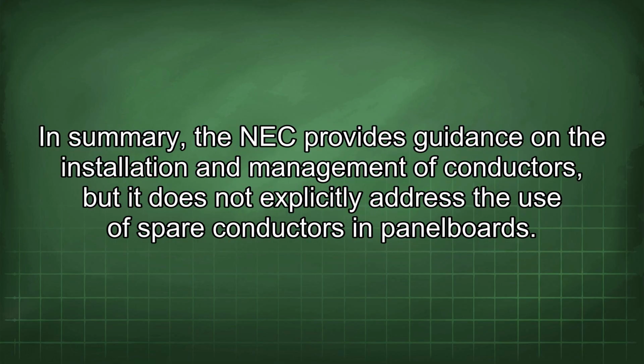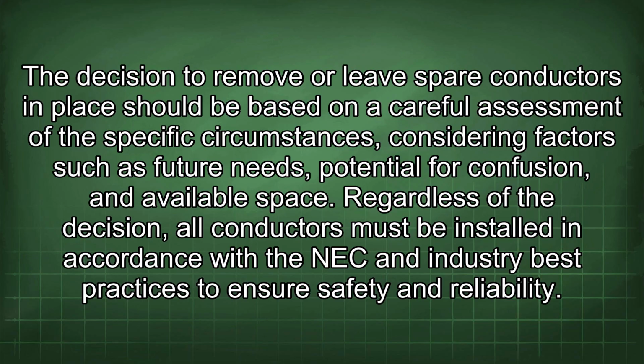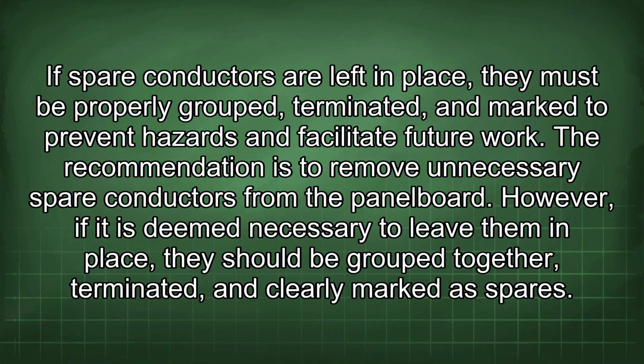In summary, the NEC provides guidance on the installation and management of conductors, but it does not explicitly address the use of spare conductors in panel boards. The decision to remove or leave spare conductors in place should be based on a careful assessment of the specific circumstances, considering factors such as future needs, potential for confusion, and available space. Regardless of the decision, all conductors must be installed in accordance with the NEC and industry best practices to ensure safety and reliability. If spare conductors are left in place, they must be properly grouped, terminated, and marked to prevent hazards and facilitate future work.